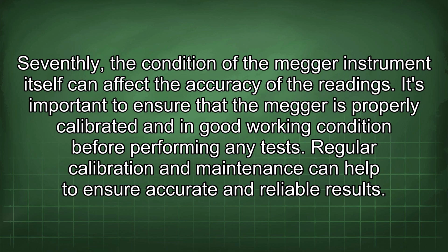Seventhly, the condition of the Megger instrument itself can affect the accuracy of the readings. It's important to ensure that the Megger is properly calibrated and in good working condition before performing any tests. Regular calibration and maintenance can help to ensure accurate and reliable results.